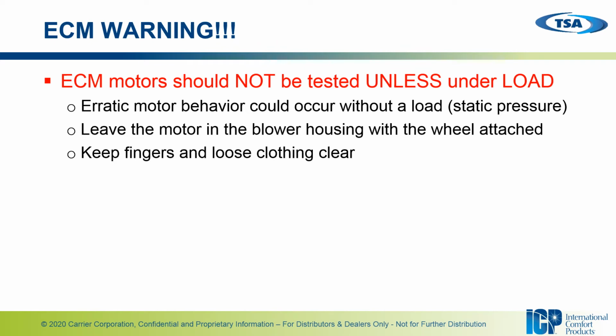Another quick issue that I'd like to point out, ECM motors, as we talked about before, they can overcome certain scenarios to an extent. All right, they are a little more sensitive to high static pressure, but then when you're testing them, they also have to have a load on them. Okay, if you disconnect the motor and you run the motor without a blower wheel attached to it, you're going to end up burning it up. Okay, so be cautious. Make sure you keep it attached to the blower wheel, to the blower housing. Otherwise, you could see erratic motor behavior. All right, you want to keep it connected to a load.